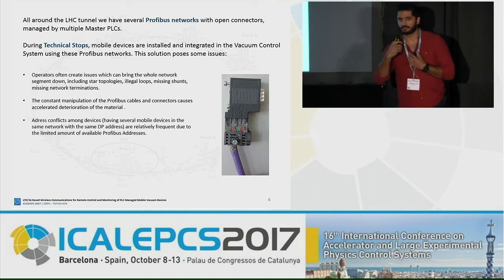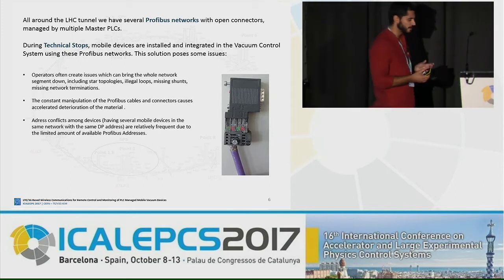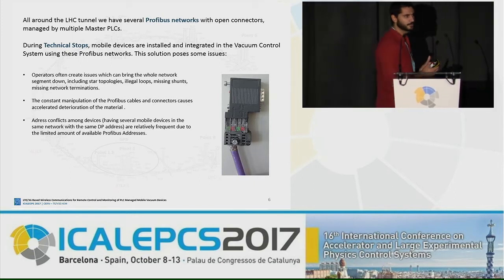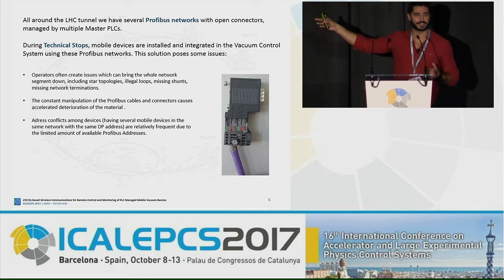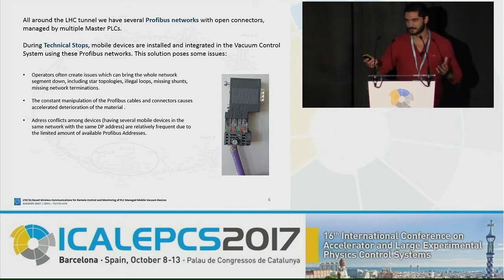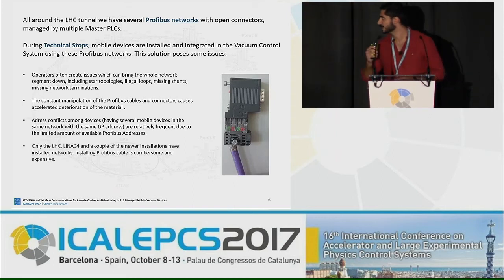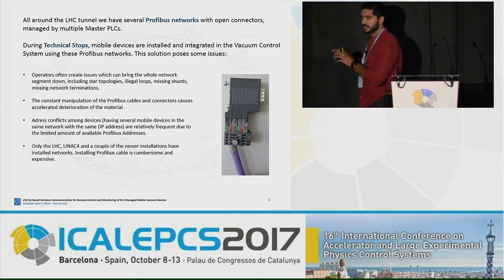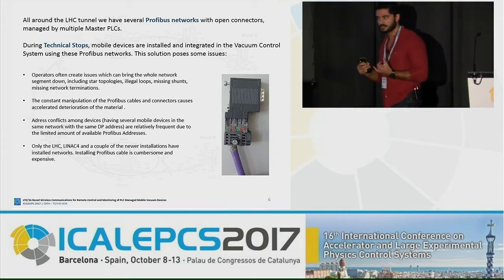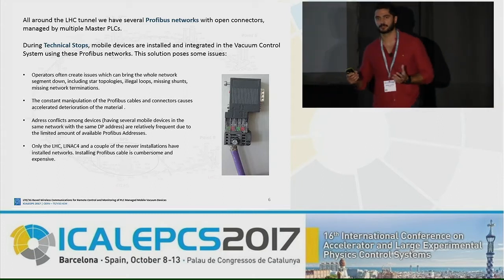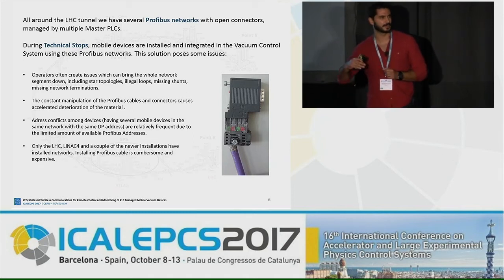Then we have the issue of address conflicts. In Profibus, we have 124 available addresses, and if you have 600 devices, you can see how this might be an issue. So sometimes we end up with address conflicts. And finally, we only have cabled Profibus networks in the LHC, in the LINAC 4, and a couple of new experiments. And it's very expensive to cable another 20 or 30 kilometers of tunnels.